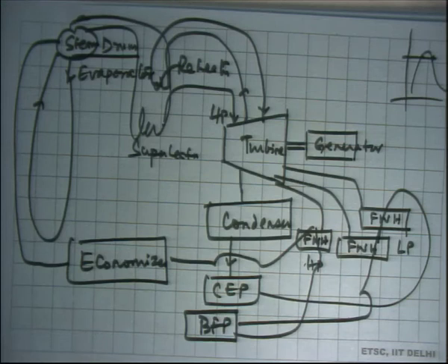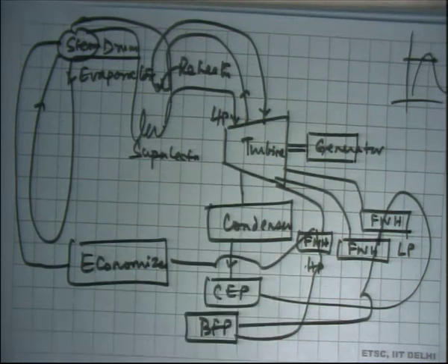Okay. So, again pumps, right. The condenser gets a huge quantity of water. The flow rate of water in the main circuit is usually about 1/500th or 1/200th of the flow rate of water that you require from the cooling tower to the condenser. The water that is in the main cycle is much smaller, but the quantity of water that flows in the condenser is huge. You can understand that because in a 500 megawatt power plant, you are actually rejecting 750 megawatts in the condenser. 1.5 times the power that you produce in the generator, you are rejecting in the condenser.